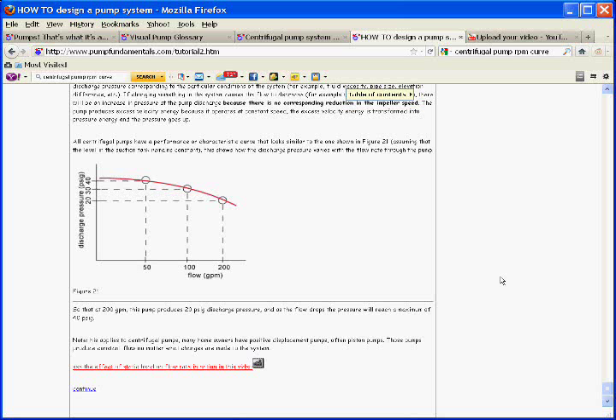So that's why when you have less flow, you're going to have a higher pressure because the impeller just keeps running at the same speed and doesn't know what to do with that water. It just creates high pressure. Now, it is true that if I'm talking about a system where I haven't changed anything except maybe opened or closed a valve, there's nothing that has been changed in the characteristics of that system.